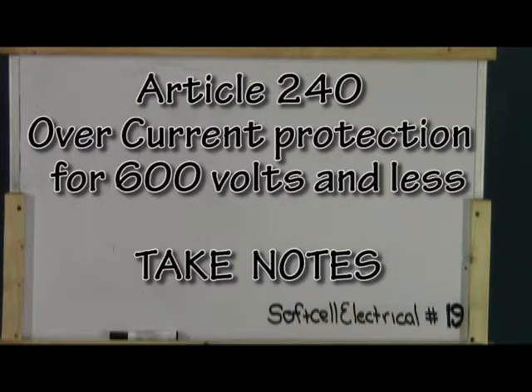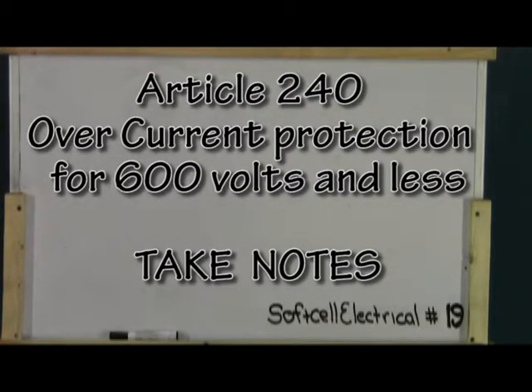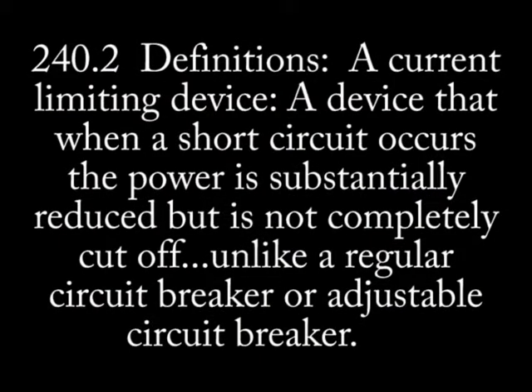Article 240 takes us into overcurrent protection for 600 volts or less. This article takes us through most of the code book. Let's start with article 240.2 definitions: current limiting overcurrent device. To simplify it, it's just a breaker that reduces the current when you have a short circuit. It maintains a substantially lower current rather than completely breaking the circuit. This type of device is rarely used, but you should know what it is.